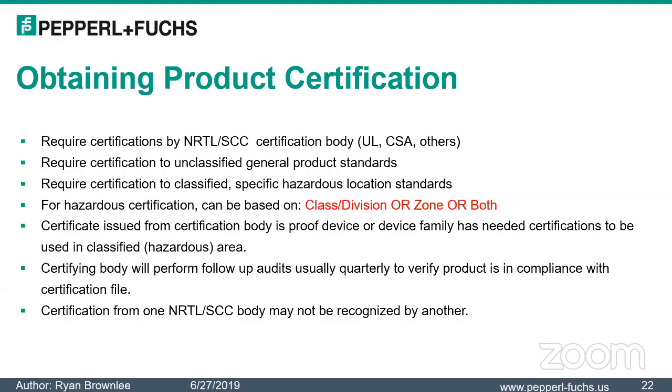I hear both flame-proof and explosion-proof, and it seems like they both reside under ATEX, but for different areas. Right, so one is North American, explosion-proof, and flame-proof is the term Europeans use for ATEX and IECEx. They mean essentially the same thing. People use them interchangeably, but the US standards say explosion-proof or dust-ignition-proof, and the ATEX standard, IEC 60079-1, uses flame-proof. That's the difference. And the other thing too is that some of the box testing requirements are different.